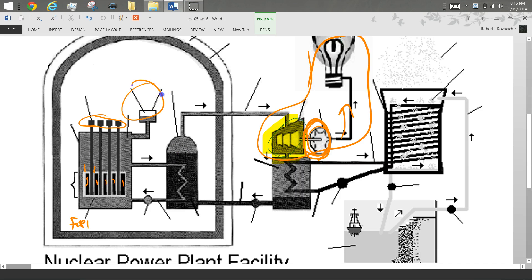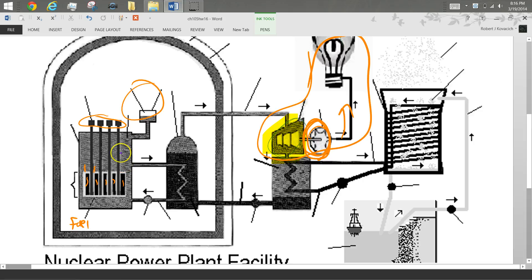This here is the pressurizer. And what that does is it makes sure that this water is at 2,000 psi. The reason I need it at a high pressure is because the water temperature is 500 plus degrees, and I can't let the water boil because steam is terrible at transferring heat.